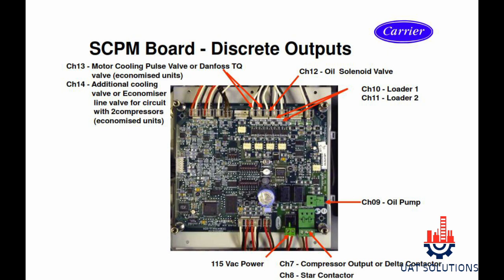Discrete outputs connected on the SCPM board: motor cooling valve connected on channel 13, additional cooling valve connected on channel 14, oil solenoid valve connected on channel 12, compressor capacity control loaders are connected on channels 10 and 11, oil pump is connected on channel 09, and compressor contactors are connected at channels 7 and 8.